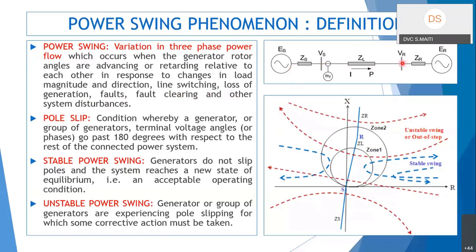If you consider a relaying location with a system behind it and a system in front of it, due to disturbances in the grid the relay may see a cyclic variation in voltage and current caused by reshuffling or rearrangement of rotor angles of the equivalent systems. Physically it is easy to understand with two generators, but you can always think of networks as equivalent generators.